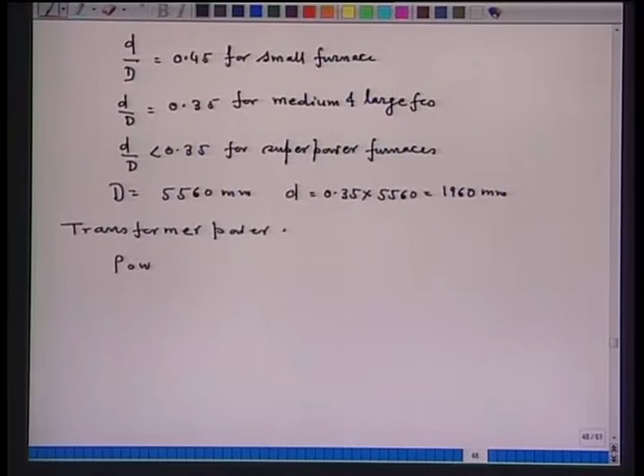So, power consumption in melting is of the order of 470 to 650 kilovolt ampere per ton for small furnaces. Now, these are just roundabout figures, you may have a different figure, but it may lie in between this range. For bigger furnaces, the power requirement is 450 kilovolt ampere per ton.